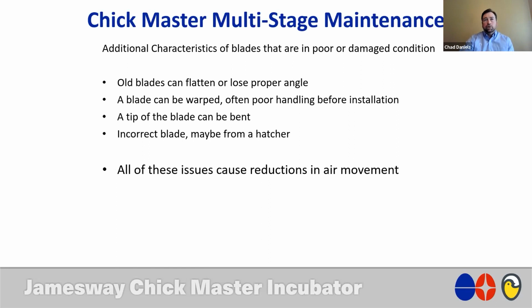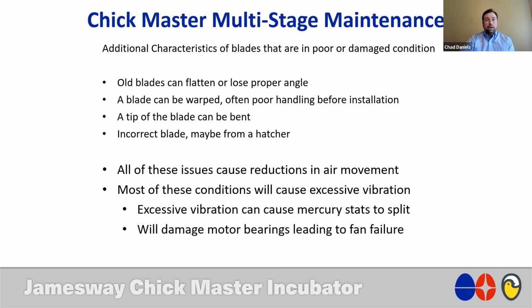All of these issues cause reductions in air movement, and a lot of times we see them cause excessive vibration. You can step into an incubator hallway a lot of times and hear a machine that's vibrating pretty badly, generally caused by the fan. Unfortunately, with older machines, this can cause mercury stats to split. It can also cause motor bearings to fail in motors. So it's critical to keep on top of making sure all of those are in good shape, because you're preventing the issues that create a bigger problem, such as bearing damage.